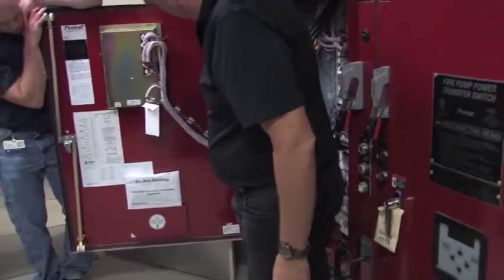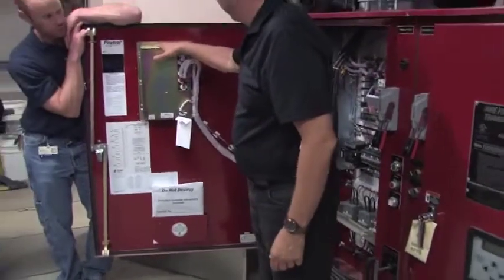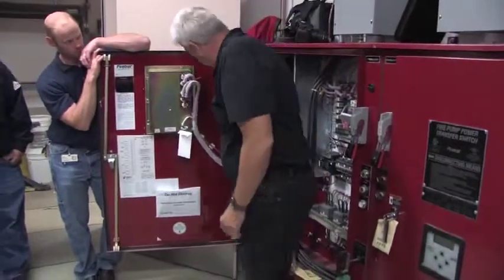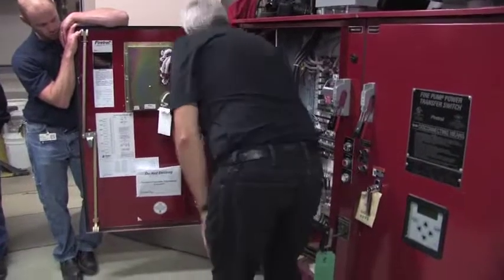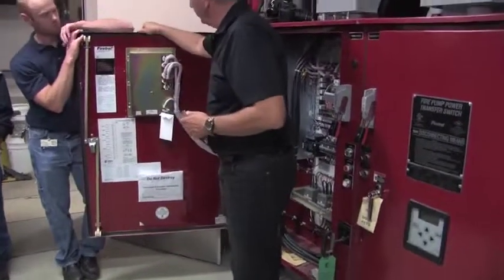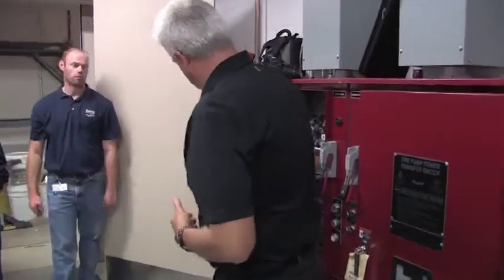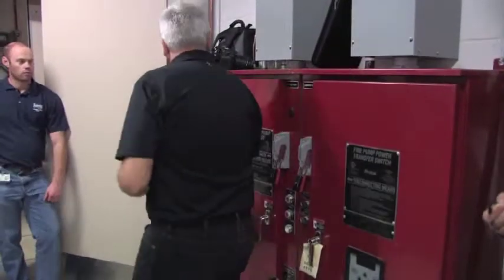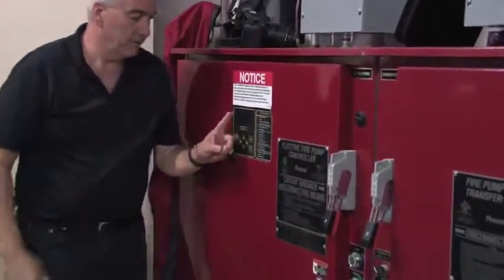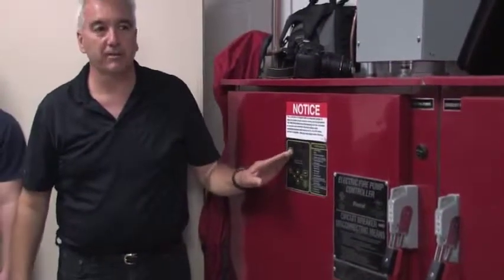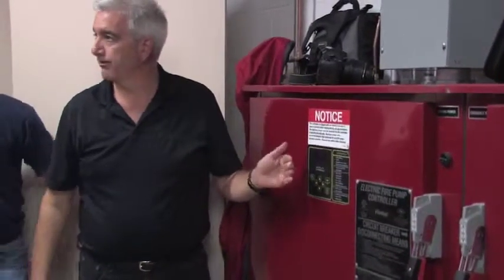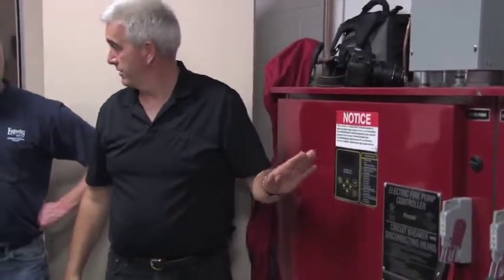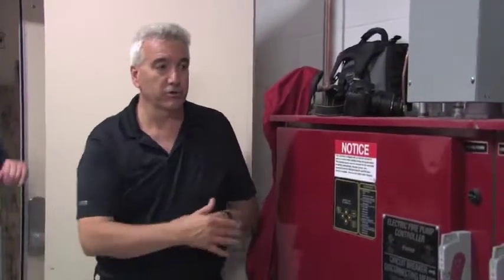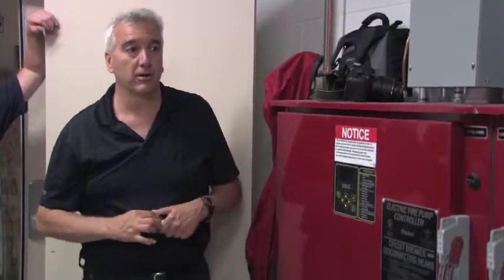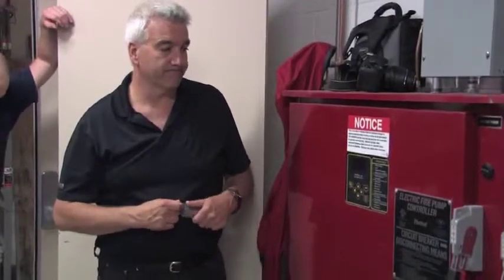And that pressure switch sends a signal to the Mark II XG. And I'll look at that in a second. But, as far as the information on the screen, it tells you at any given time what the system pressure is, the time and the date, and what the voltage levels are. And when the pump runs, it gives you the three-phase current as well, right in front of the door. Because by code, we have to build controllers now so that you don't have to open the door in order to test them and take readings.